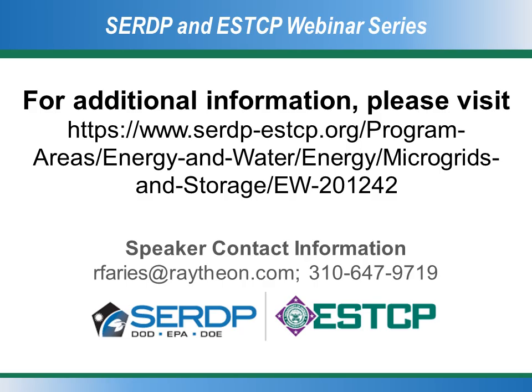So the flow batteries themselves do require a certain amount of maintenance right now. Because we have Primus's first systems in the field, we're learning about the maintenance of that particular aspect. The electrolyte they use needs to be monitored to make sure it's operating in its sweet zone. They have some level of controls that monitor it and add elements to keep it operating at what they think is the most optimum mixture, their secret sauce. Right now, they're having to spend more time out there because they're learning how to maintain this system, and they're putting that information into their Gen 2 designs, because the one that we have is basically the prototype out of the gate.